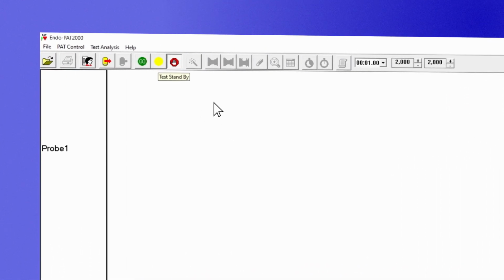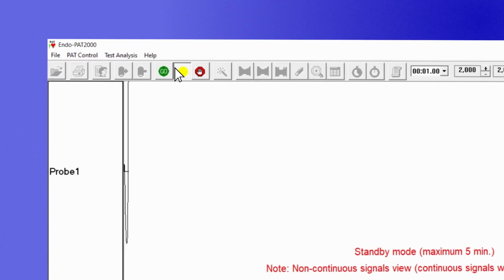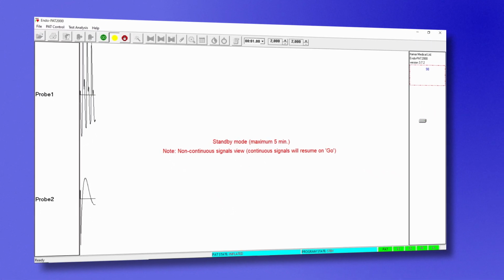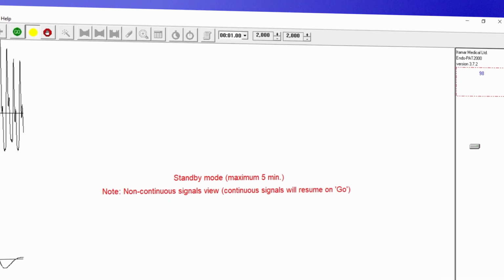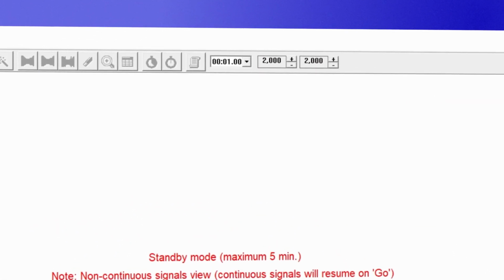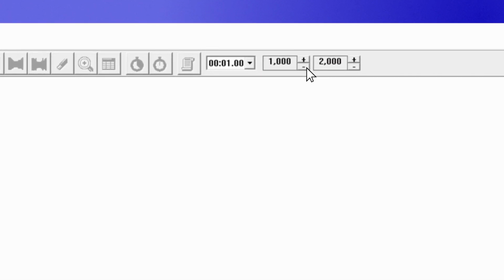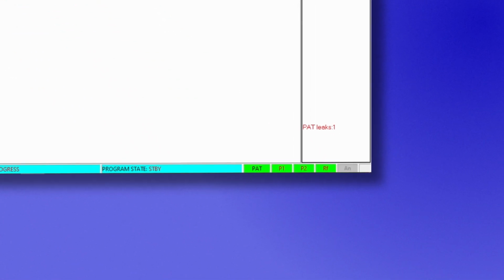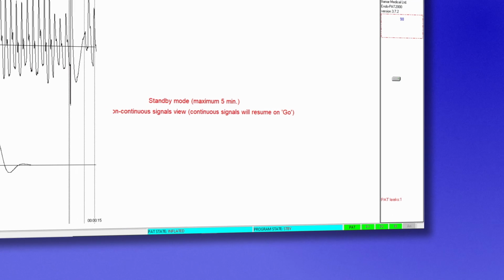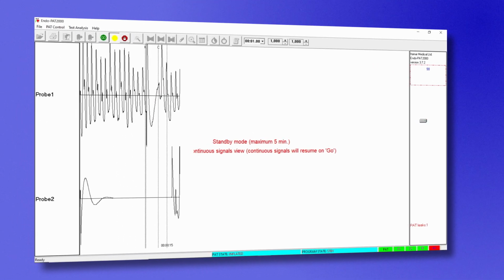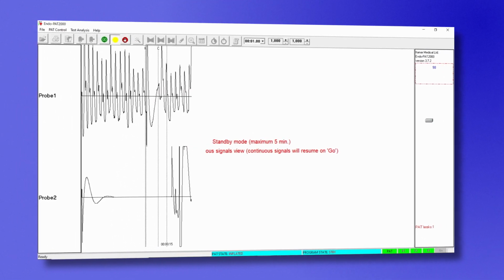Select Standby. Adjust the gain of the signal for optimal view and inspect the quality of the signal for 1 to 2 minutes. If leaks are detected, a warning will appear on screen, counting the leaks from the probe. A few leaks in the first 2 minutes are normal until the system stabilizes.